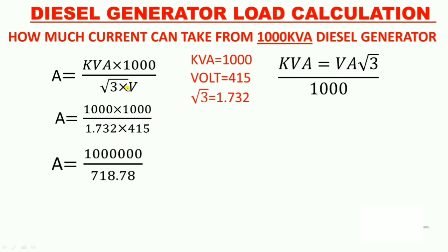Now if we solve this formula: solving the denominator, 1.732 × 415 = 718.78. Solving the full expression, ampere = 1,000,000 / 718.78 = 1391 ampere. So, if we have a 1000 kVA diesel generator, the full load current is 1391 ampere.